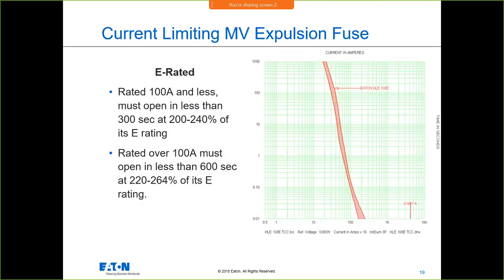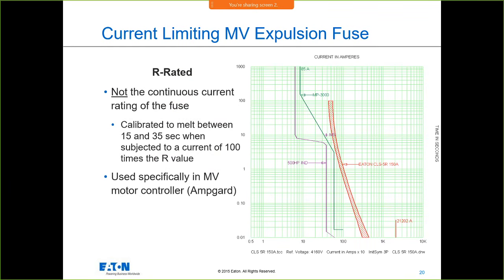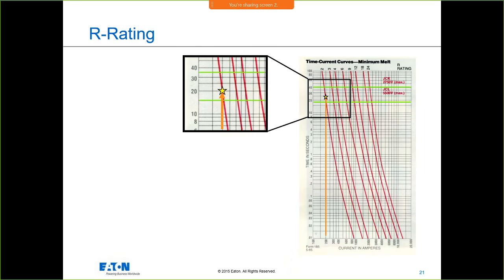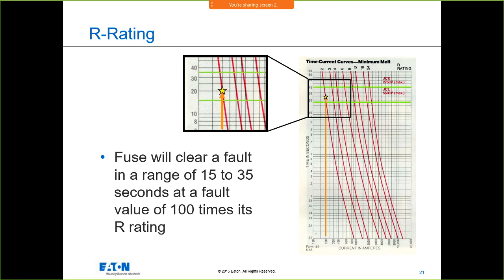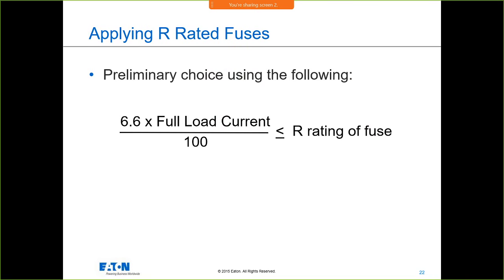All right, back to this. So there's your medium voltage. When you get into these big motors, they're going to invest in a relay, and then you'll have your medium voltage fuse to help reduce your short circuit damage. Your R rating: there's a certain area in these fuses that you don't want to operate in. The fuse is going to clear in a range of 15 to 35 seconds at a fault value of 100 times its R rating. That's where that point is on that curve. This is how you preliminarily choose the fuse. You do some simple math and you'll get a ballpark of where your rating needs to be.